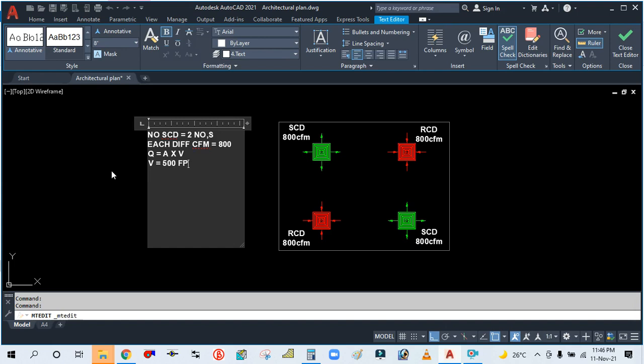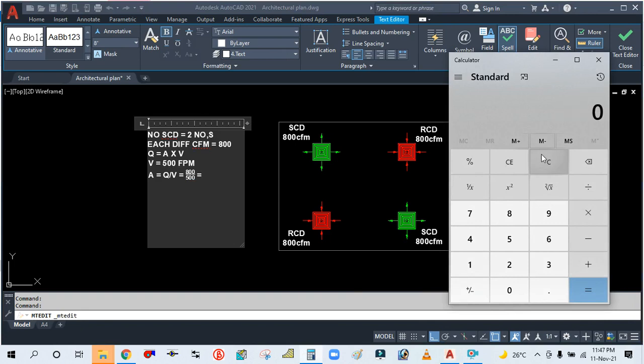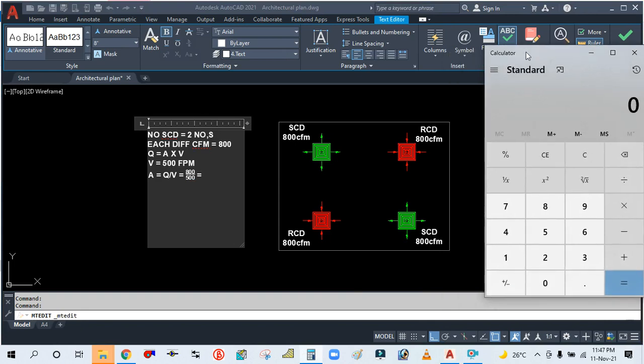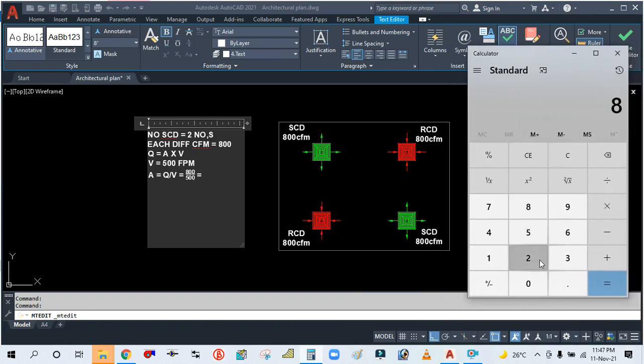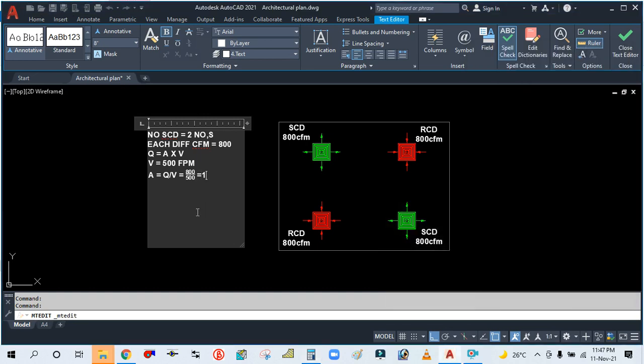So from this equation, you have to calculate area. A is equal to Q by V. Q is 800 CFM divided by 500 feet per minute. So 800 divided by 500, we are getting 1.6 square feet.